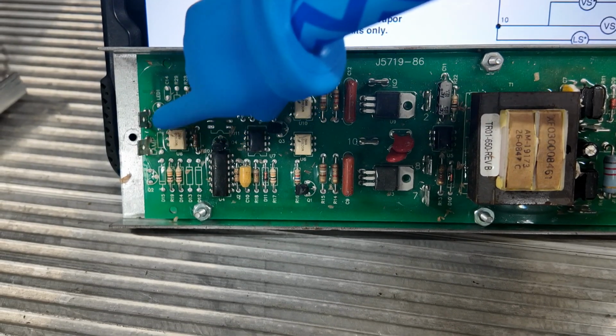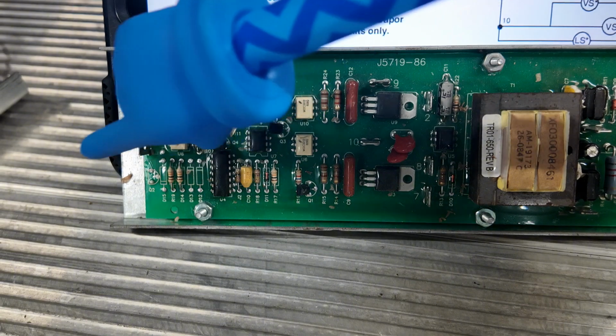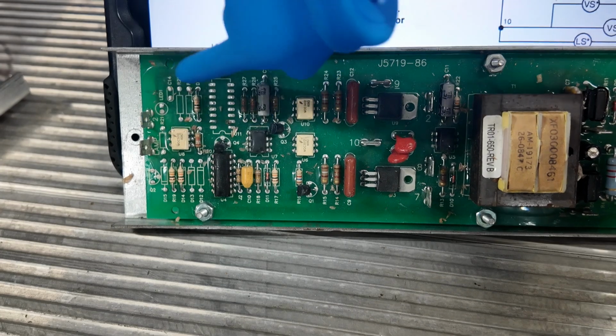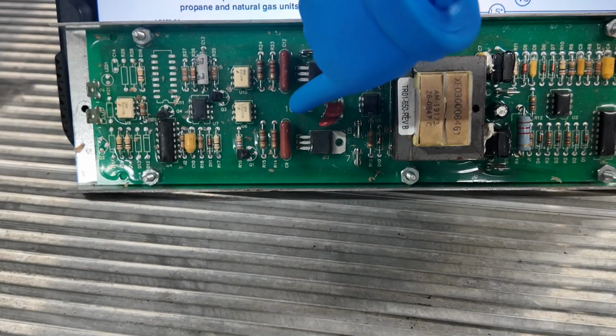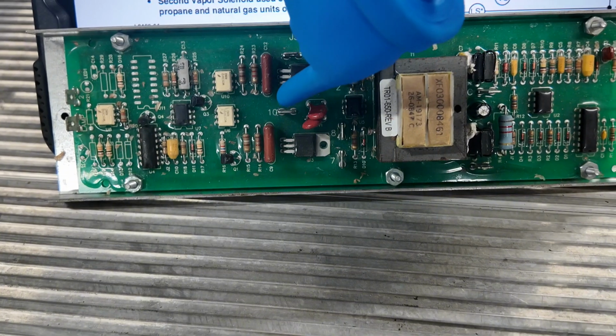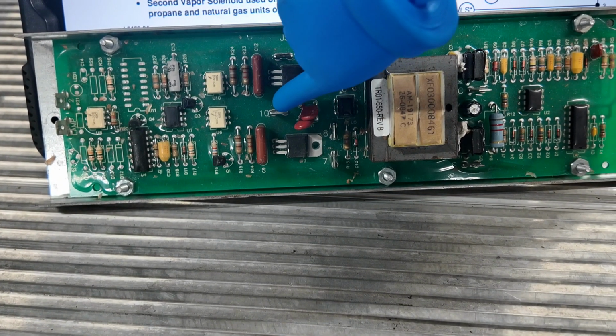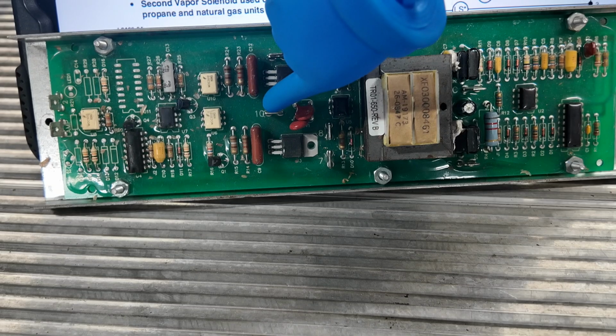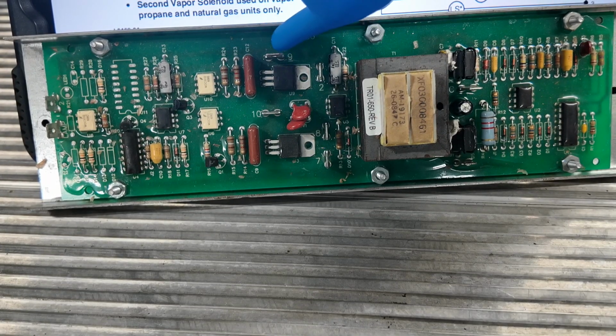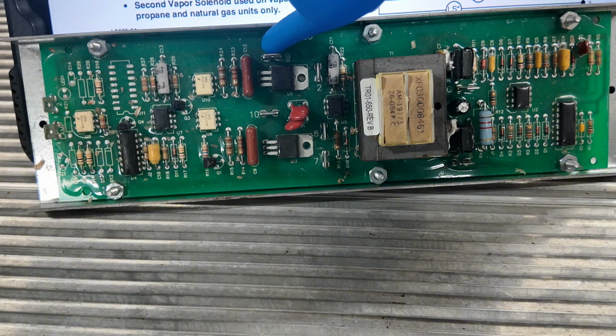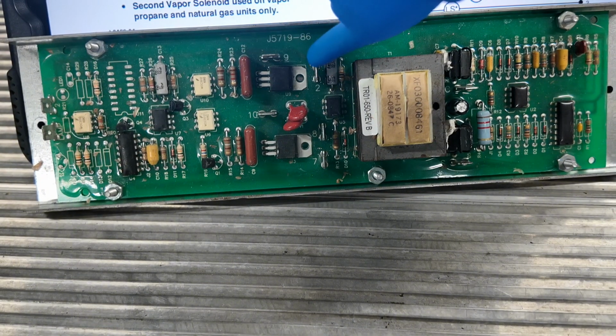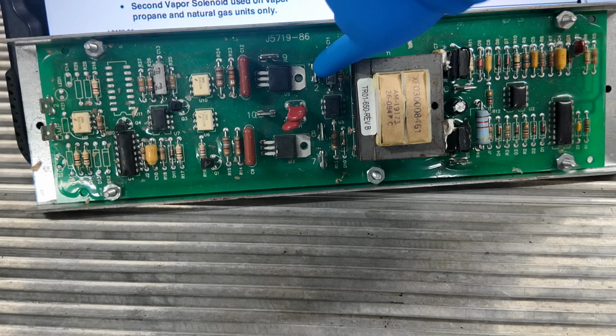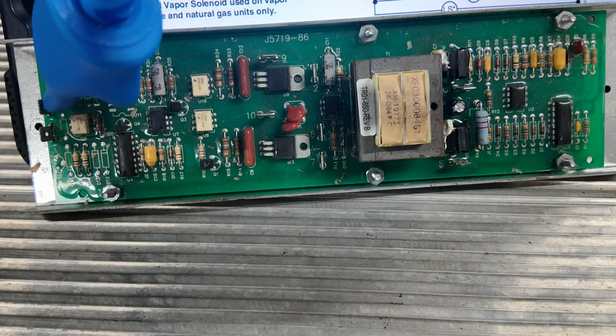So here on this end, we have these two spades. We have a terminal 2 and a lamp. The lamp would hook to the one side of the lamp. The other side of the lamp would hook to your incoming power on 7. 2 would go to neutral. Come across here, we have 10. 10 is your outgoing voltage to power the gas valves. Terminal 9 would power your ignition transformer. 2 would again go to the neutral, terminal 2. Terminal 2 here and 2 here are both just connected to the incoming neutral.